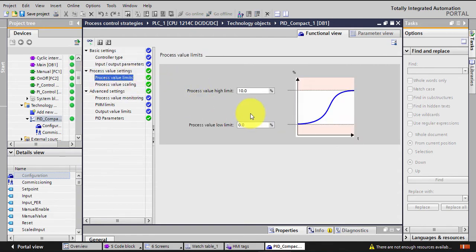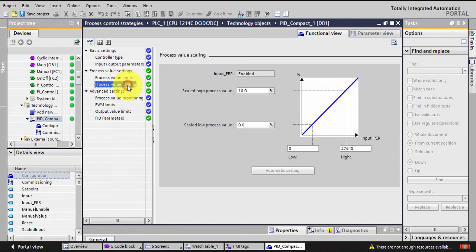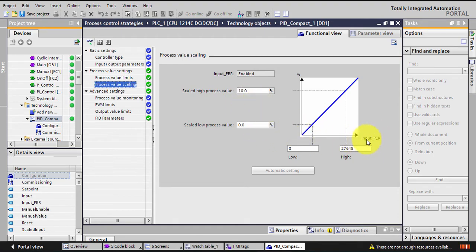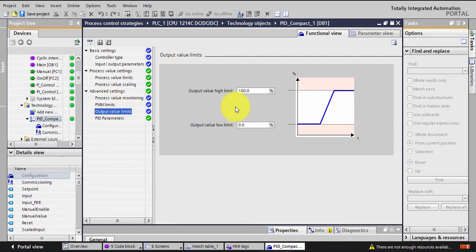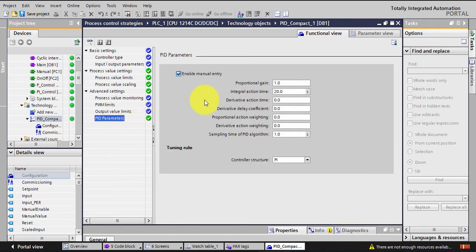The process input low limit is 0 and the high limit is 10. I'm working with light intensity but treating it as a voltage, so 0 to 10 volts. For the process value scaling, if I'm reading 27,000 that means 10 — the scale high of the output — and if it's 0 that gives me 0. The output value is 0 to 100 percent.